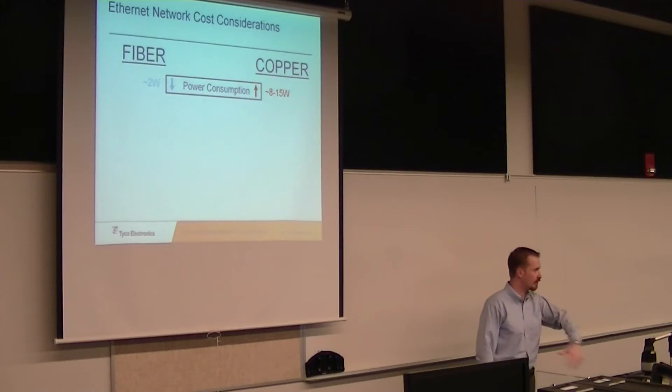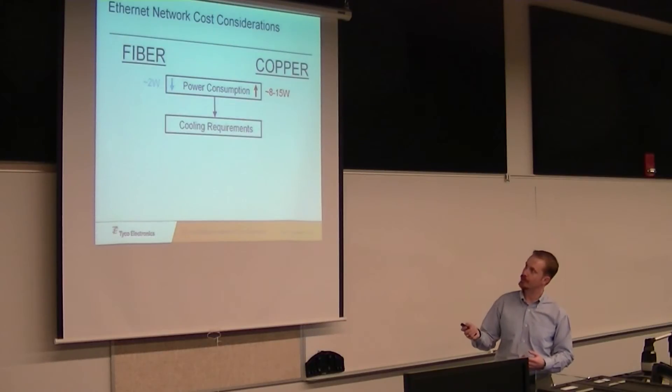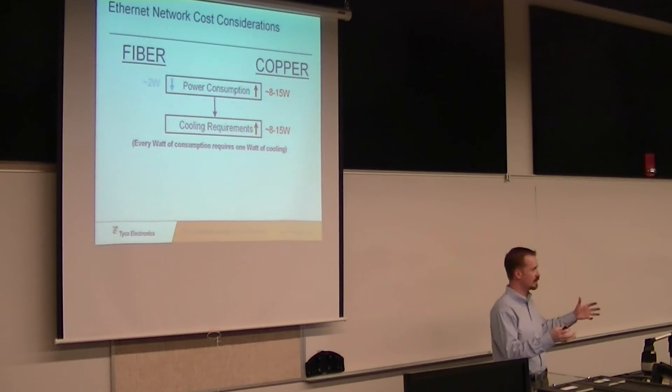In data center stuff, you have a hot aisle and a cold aisle, so you really need to maintain your temperature. But in order to cool things, for every watt of consumption requires one watt of cooling. So we need another 8 to 15 watts of power to run the cooling system to bring that temperature back down from the power consumption that raised the temperature. On fiber, we're down about 2 watts. So between your power consumption and your cooling requirements, your whole energy cost is still less than just the power consumption of copper.